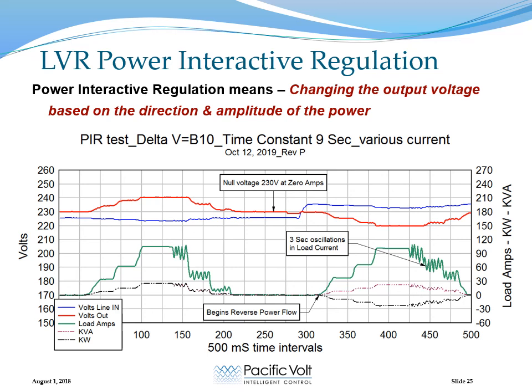This is another way to describe this feature. The red line is the output of the regulator. The blue line is the input voltage to the regulator. The green line is the load current passing through the regulator. This black line is kilowatts. So you can see as the current rises, the output voltage is increased in proportion to the current. And here there are some current oscillations provided to illustrate the dampening effect, which you have control over. That's the time constant here.